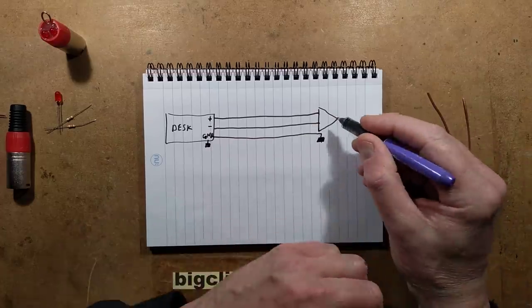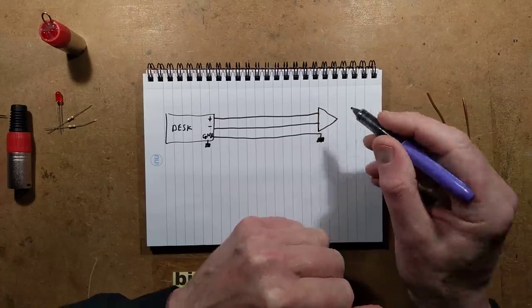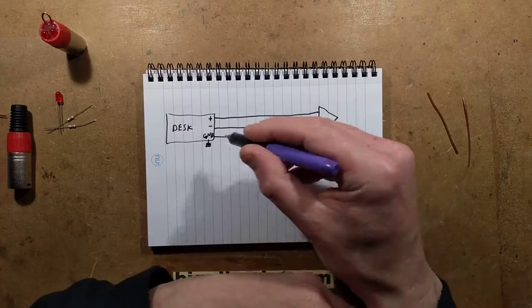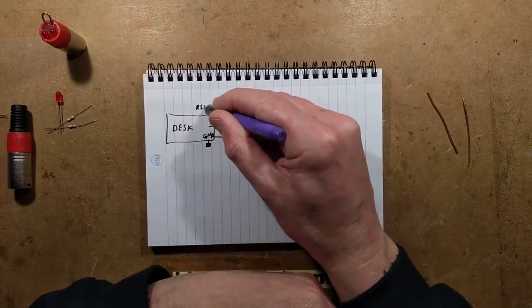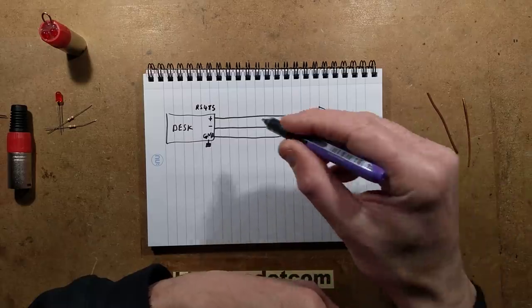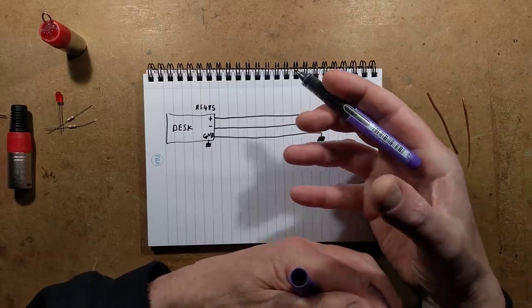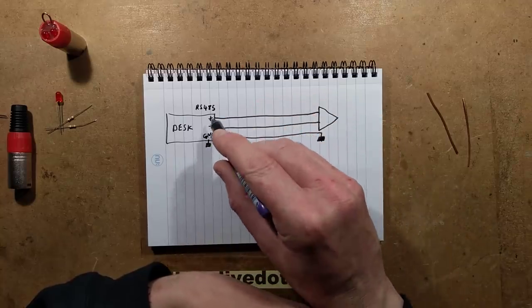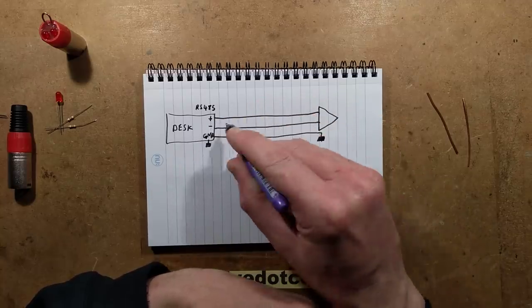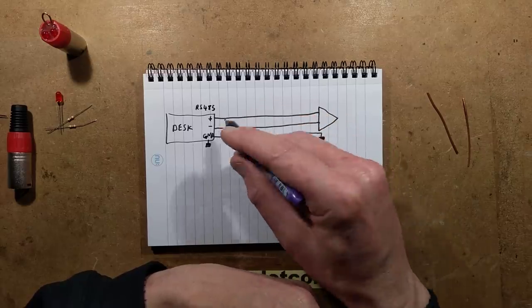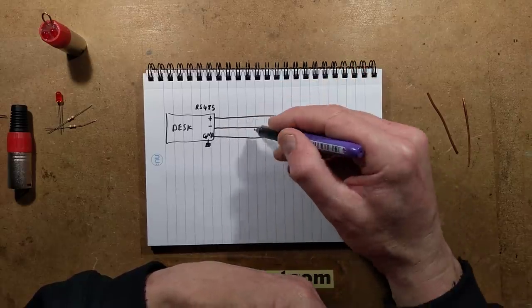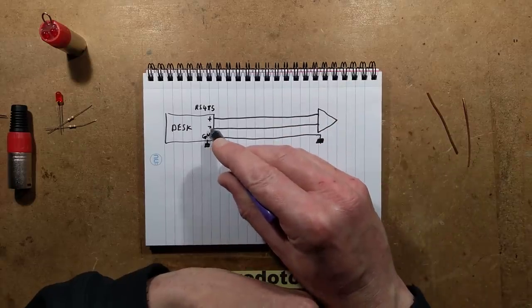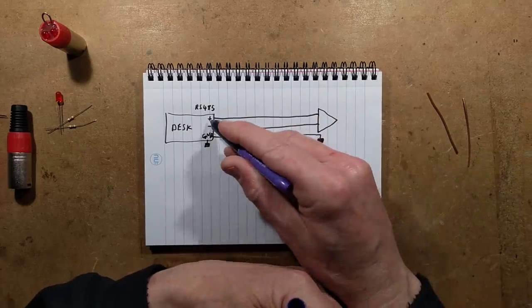The receiver has the ground connection connected to its electronic reference ground as well, and then it loops on to the next slave. The data is transmitted using an electrical standard called RS485, which is capable of driving cables quite hard, and running signals long distances by having a fairly low impedance. It can actually put quite high current out to these, even though it's just about 5 volts.